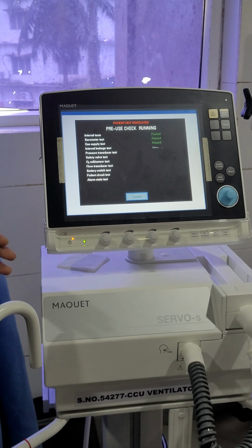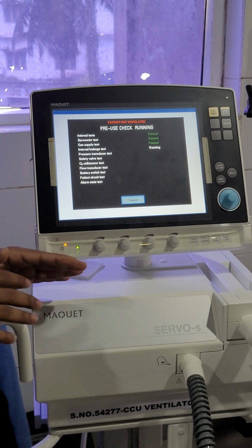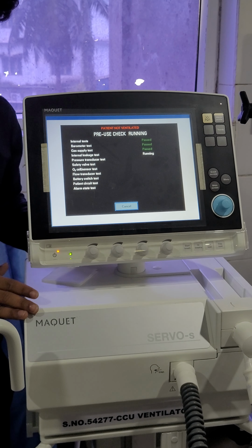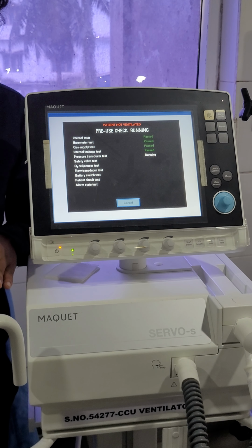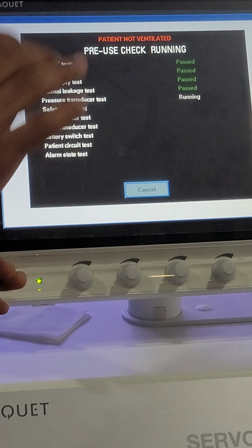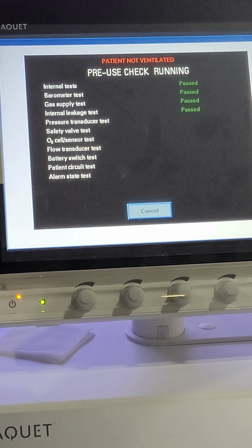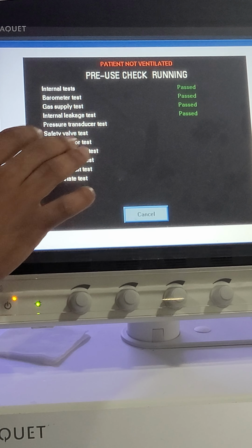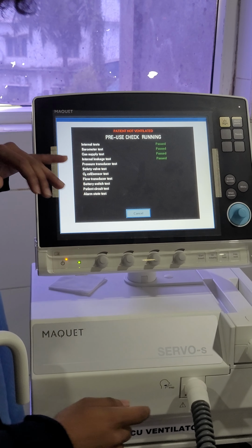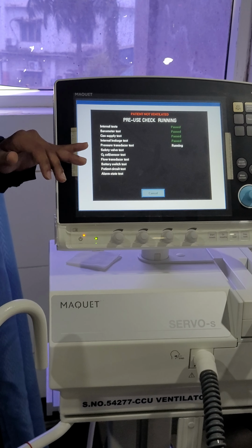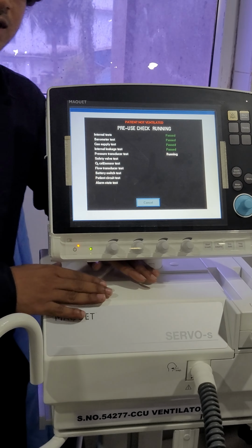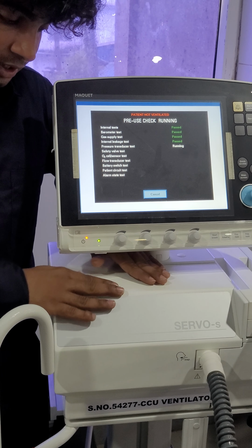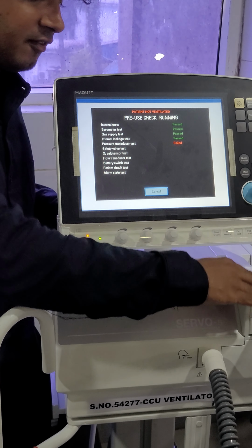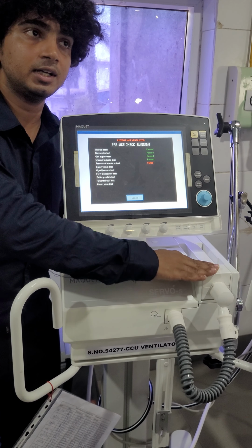Internal leakage: whether any leakages are there in the module. The ventilator has modules for air as well as oxygen. If there is any leakage in them, it will indicate. Pressure transducer, flow transducer, safety valve. Safety valve is here. Pressure transducer, flow transducer, oxygen sensor. The oxygen sensor is on the inspiratory side of the ventilator. The flow sensor and pressure transducer are on the expiratory side.